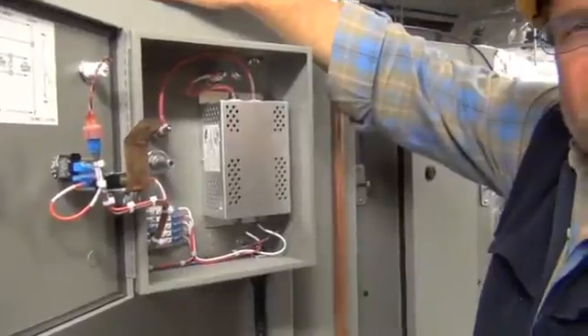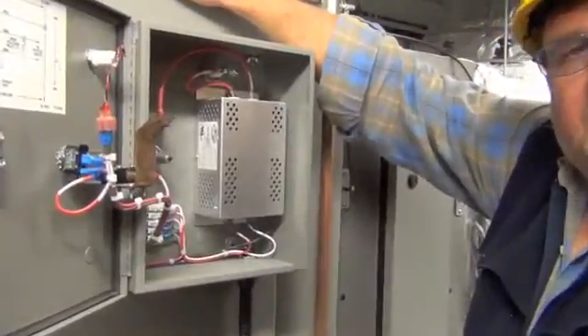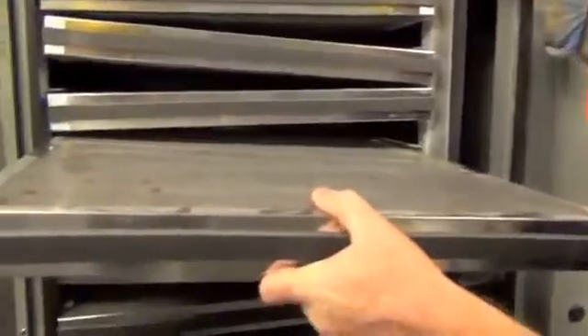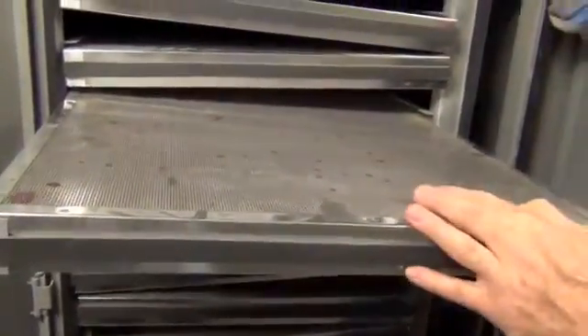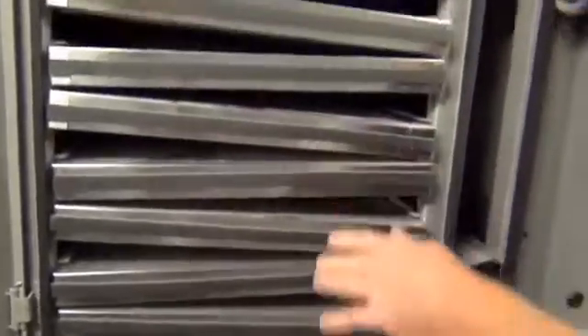Precipitator cells are powered by a solid-state transformer which converts household current into 2 outputs, a direct current at very high voltage at 10,000 and 6,000 volts respectively. This unit incorporates 3 different rows or passes of these precipitator cells to handle a very heavy loading operation. After the precipitator cells have removed all of the solid and liquid particulate, grease particles, and smoke particles, what is left is molecular odor, consisting of hydrocarbon molecules that we all smell as part of the cooking process. The final stage of filtration are these odor media trays filled with a potassium permanganate odor media which oxidizes hydrocarbon molecules as they pass through the screen side of the trays, leaving us with clean air exhausting from the Smog Hog through the exhaust blower fan.